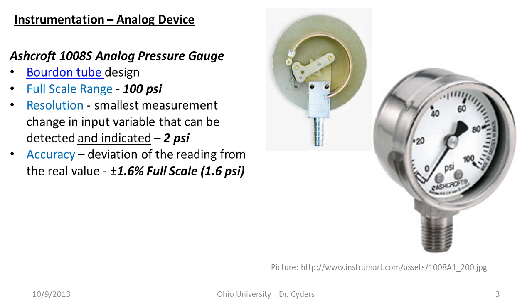Accuracy is different from resolution. The accuracy of the device is the deviation of the reading from the real value. If I put exactly 14.7 psi into this gauge, would it read 14.7 perfectly? No — there will be statistical variation from unit to unit. The manufacturer specifies accuracy on a datasheet. For the Ashcroft gauge it's 1.6% of full scale, so 1.6 psi either way. If I'm reading exactly 60 psi on my scale, the actual pressure going in is somewhere between 58.4 and 61.6 psi — standard error based on the Young's modulus of the material and other factors.